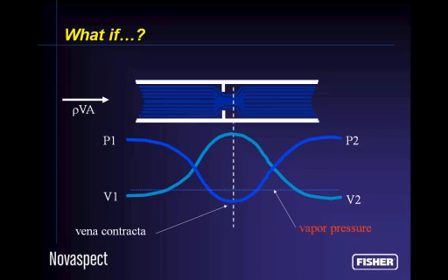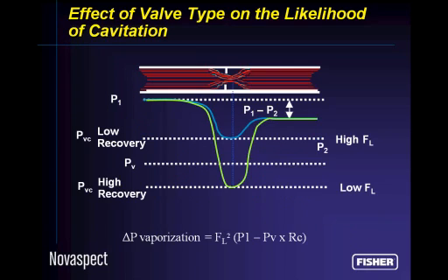And this could happen, I've seen it happen in a week, and I've seen it happen over the course of years. And it's fairly unpredictable, actually, as to how it will affect you. It depends on the materials of construction, how fast the fluid is flowing. A lot of different issues come into play here. But the fact of the matter is we are cavitating, and cavitation will cause damage, and it's just a matter of how long it takes before you're calling us for a new valve or new parts, or you're calling our repair service to come out and fix the valve.